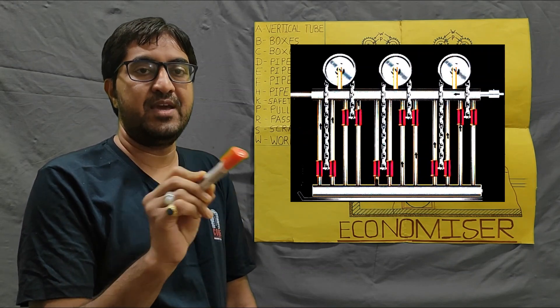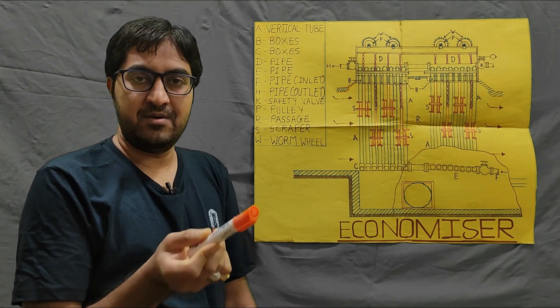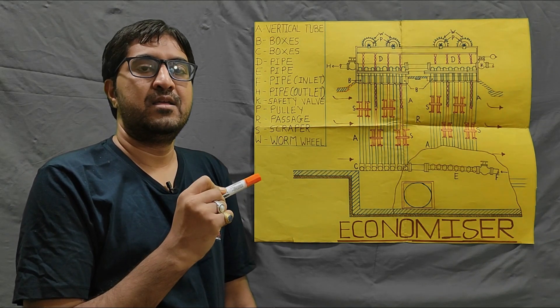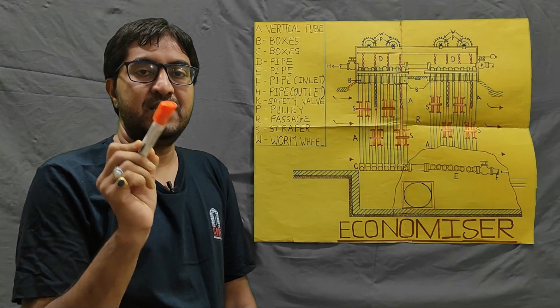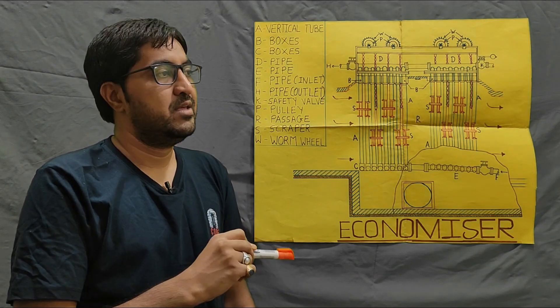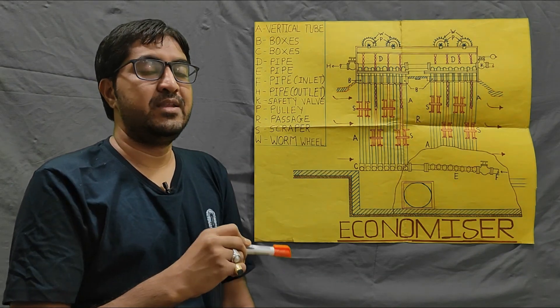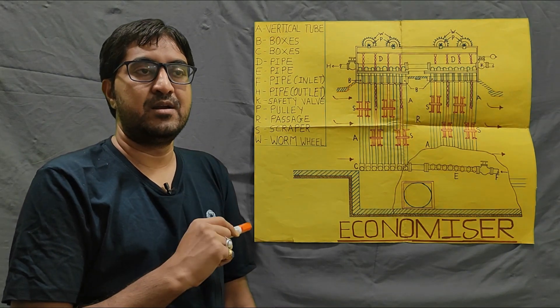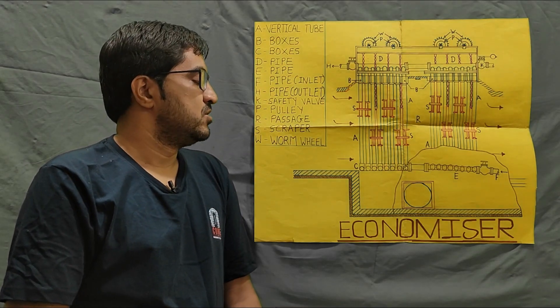First of all, what are mountings and accessories in the boiler? Mountings are those parts that are necessarily required in the boiler — without them we cannot operate the boiler. Examples include the safety valve, water level indicator, and pressure gauge. Accessories are those parts which are not compulsorily required but are used to increase the efficiency of the boiler, like an air preheater or economizer.